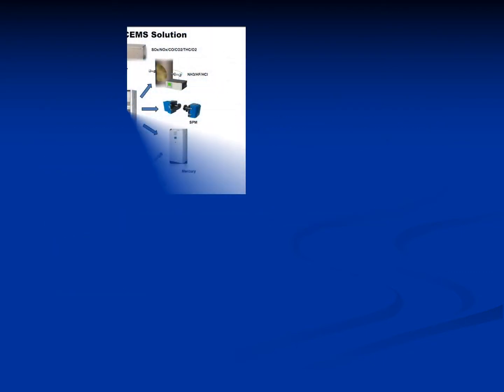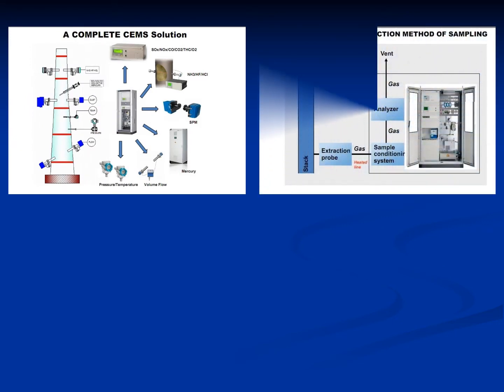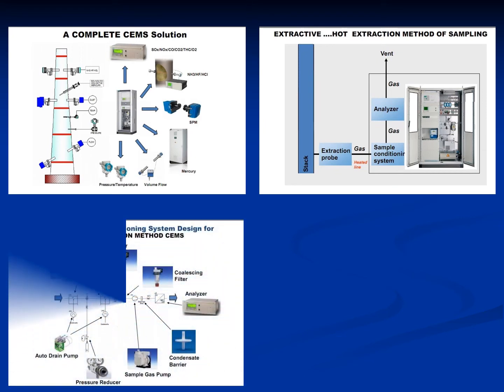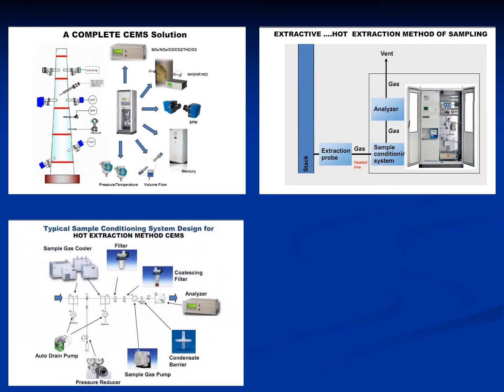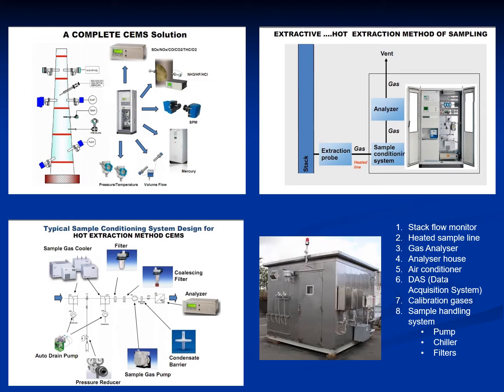In this picture, you can see all the parts which make up a typical CEMS, and how all these parts are interconnected. This shows an overview of how the sample handling system works, and this is a typical analyzer housing. As you can see, there are more than eight major parts of a CEMS, which includes the stack flow monitor, the heated sample line, the gas analyzer, the analyzer house, air conditioner, DAS (the data acquisition system), calibration gases, and the sample handling system, which has several other parts including the pump, chiller, and filters.